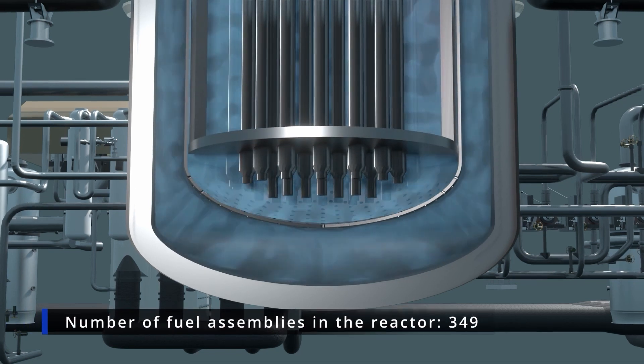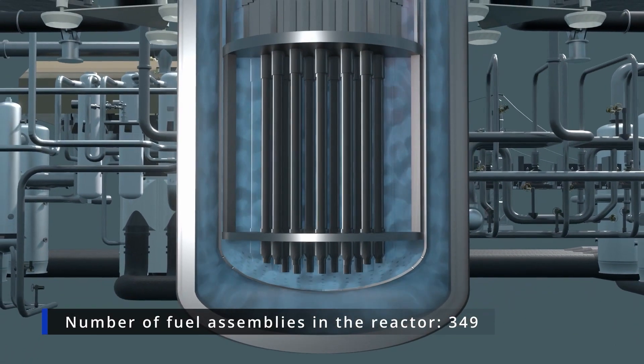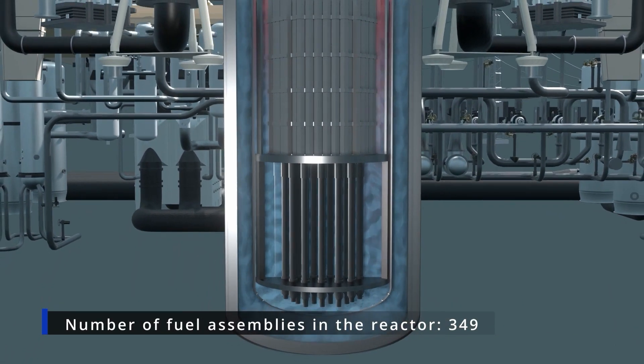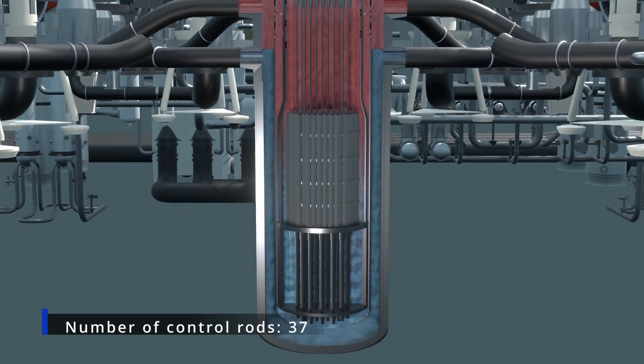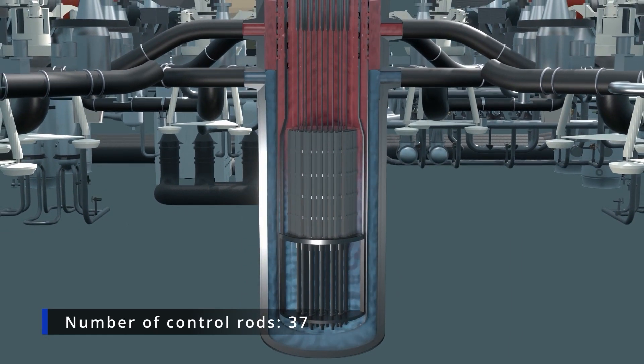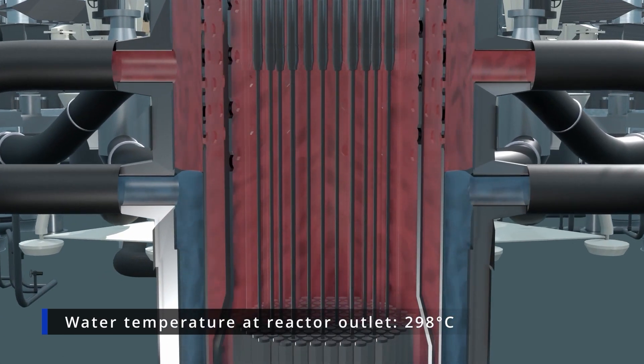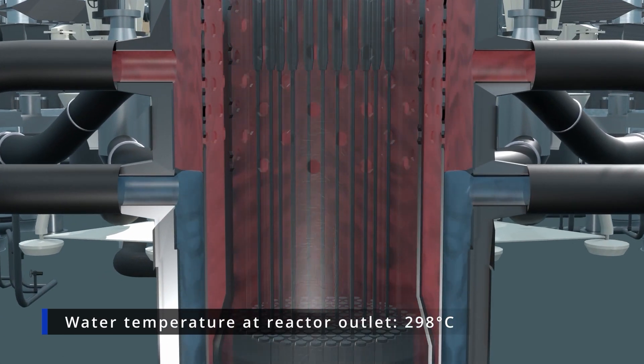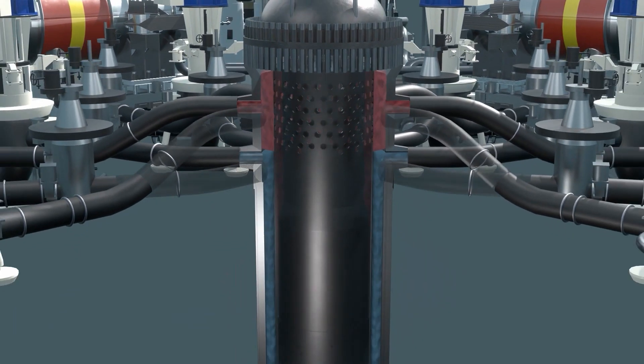It flows through the reactor core, which contains 349 fuel assemblies, 37 of which also have a boron steel superstructure. These control cartridges can be moved up or down in the core to increase or decrease the reactor's heat output. Heated water exits the reactor pressure vessel through the top spigot at a temperature of just under 300 degrees Celsius.